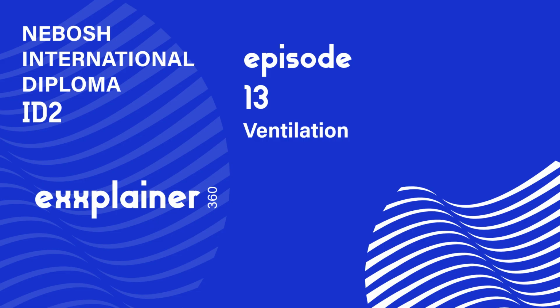Makes sense. And even if you can use DV, fan placement isn't just sticking a fan anywhere. Not at all. It's basic physics, really. Density. Density of the contaminant vapor. Is it heavier or lighter than air? Most common solvents, their vapors are denser than air, heavier than one. So they sink. They layer near the floor. So for those, you need extraction fans low down on the walls. And if it's lighter than air? Then it rises fast. So you need fans high up, maybe roof fans. Get it wrong, and you're just swirling it around, not removing it effectively.